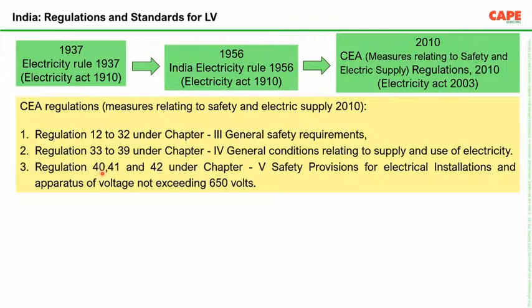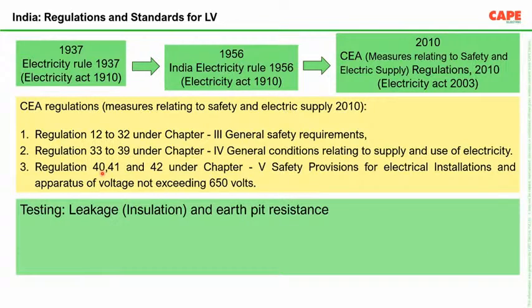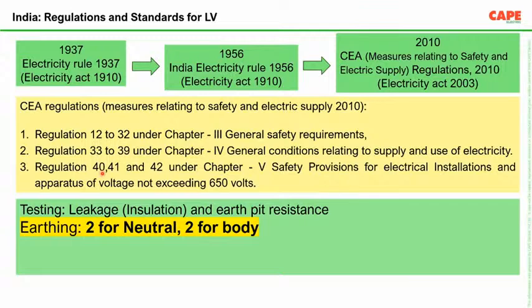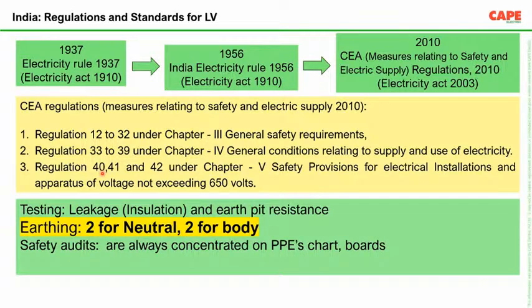As a result, what we do mandatorily is only the insulation resistance test and the earth pit resistance test. Unfortunately, the second one, the earth pit resistance test, has nothing to do with safety in a low voltage system. Now, the practice which we follow across India is 2 for neutral, 2 for body. That is, the transformer neutral has 2 separate and distinct connections to earth pit, the transformer body has 2 separate and distinct connections to earth pit, and the generator is separate. Actually, these are misinterpretations. It is not written in the regulation or in the standard, but somehow we started reading the regulation in this fashion. I will explain with an example in the next slide.